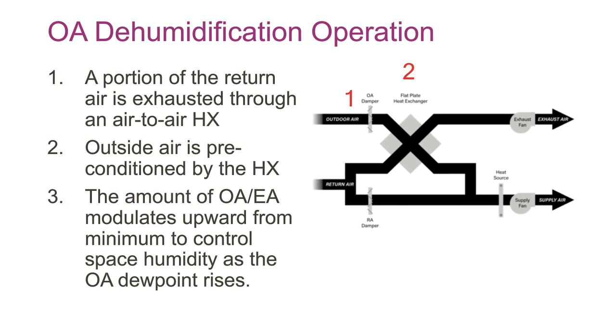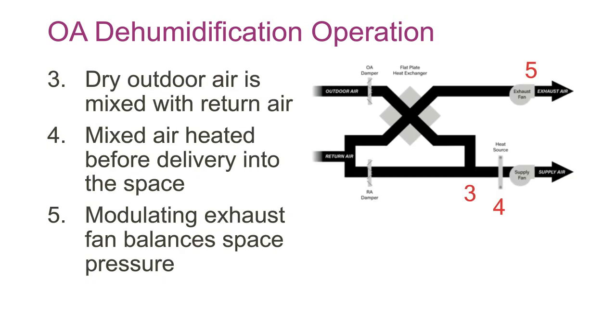So the operation of that type of a system says, well, we're going to bring a portion of the outside air in and then have that go through the air-to-air heat exchanger. The outside air is preconditioned by that, and then the amount is going to modulate upward as you come into the shoulder season, spring and fall and summer, where the minimum outside air is no longer doing the dehumidification. End up mixing the dry outside air with return air and then deliver that to the space. And typically the exhaust fan modulates on pressure to control your space pressure at a slight negative.